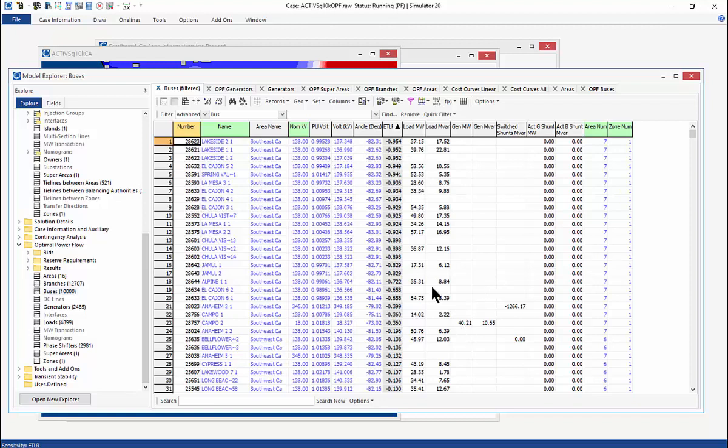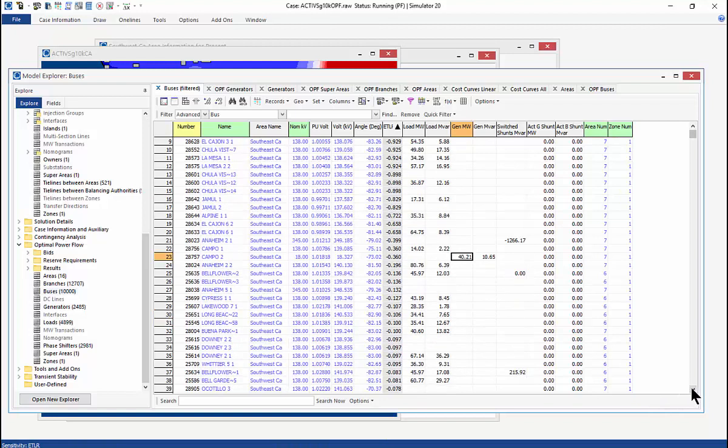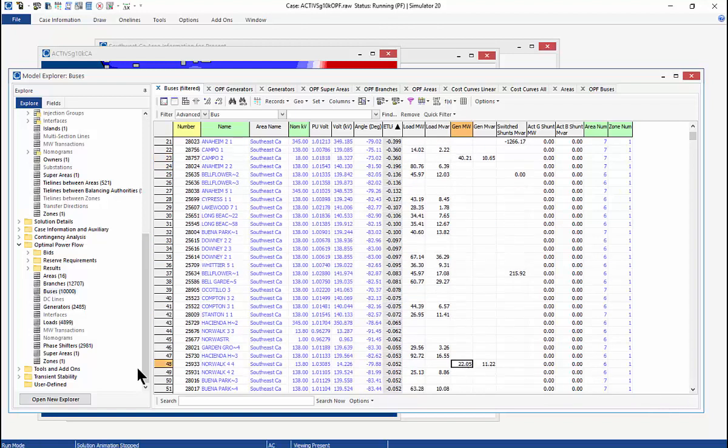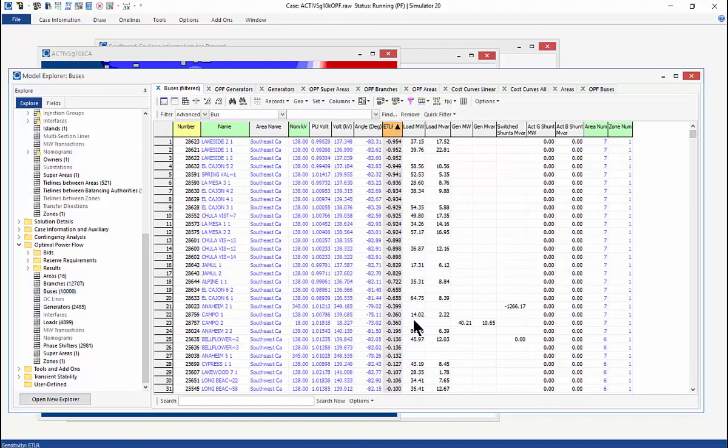But there's no generation there until you get down here, and that's a wind generator. And then you keep going, and you don't see any other generators. I don't know, this might be wind too, but now the sensitivity is getting lower. So we could try to see what the impact would be of using load benefit models and demand response at some of these loads.